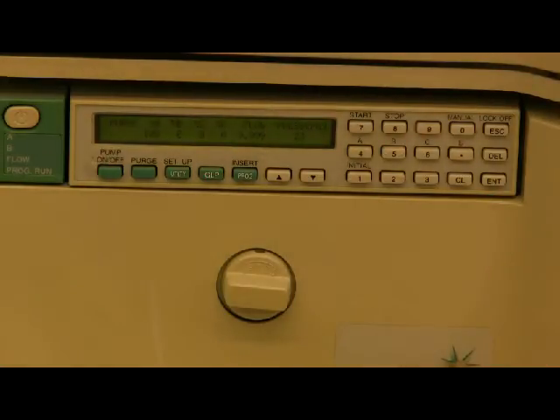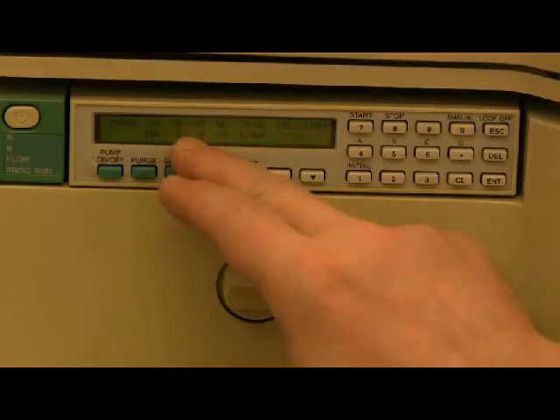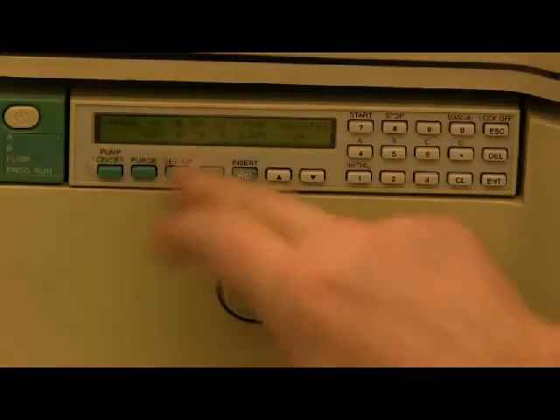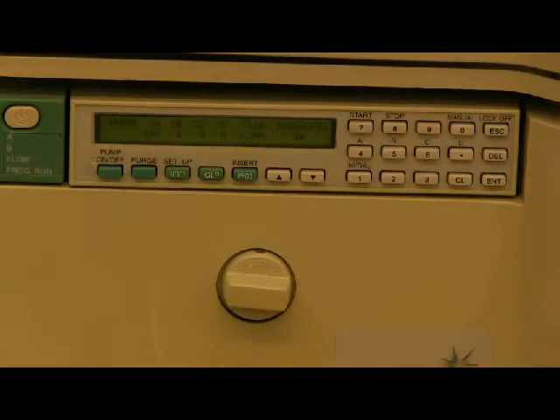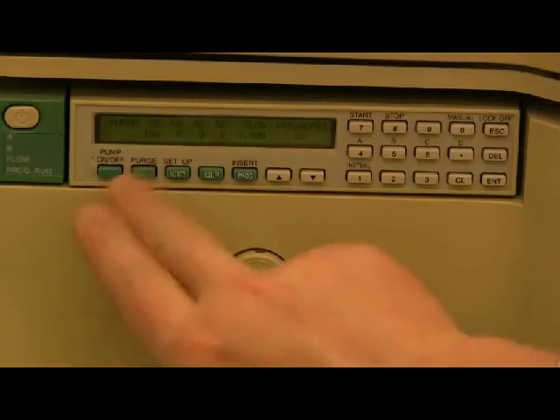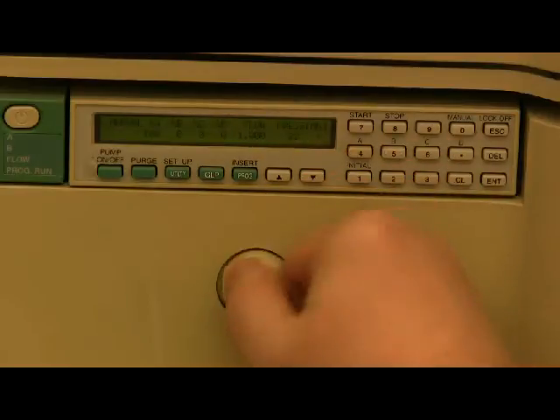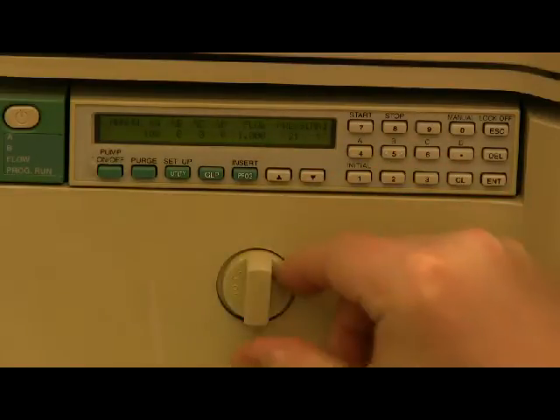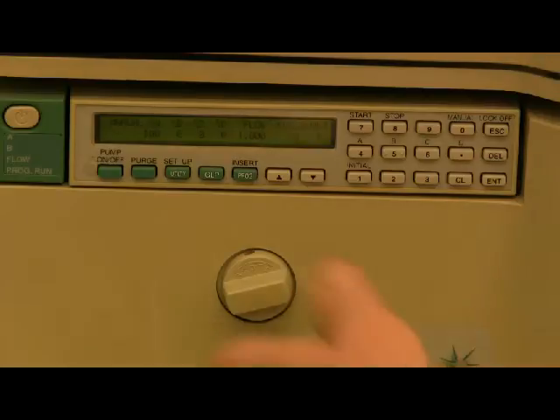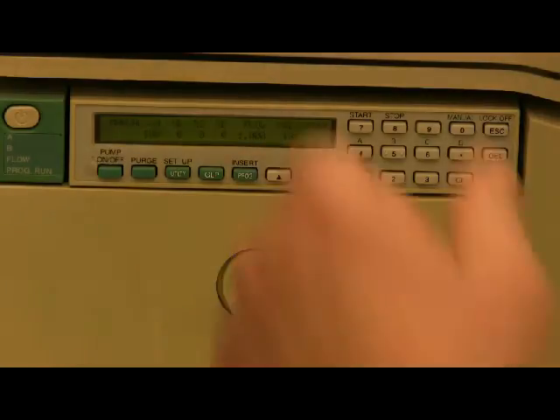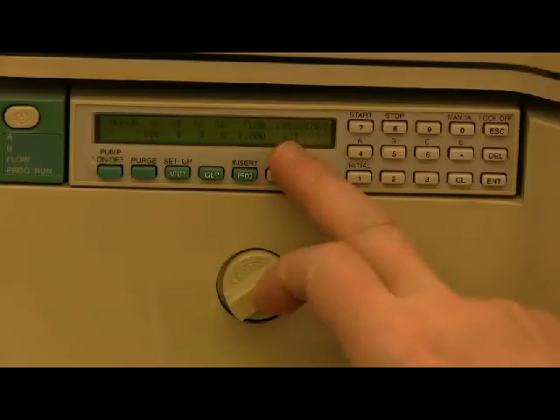Depending on how much mobile phase you have, you can let it run for a while to make sure that all the lines are purged of air. And if you're running a gradient for a different lab, you'd have to change the concentration, the percent of mobile phase running through each line and purge each line, A, B, C, or D. So then to stop it, you hit purge again. Tighten this back up. And you can see your pressure's climbing back now.